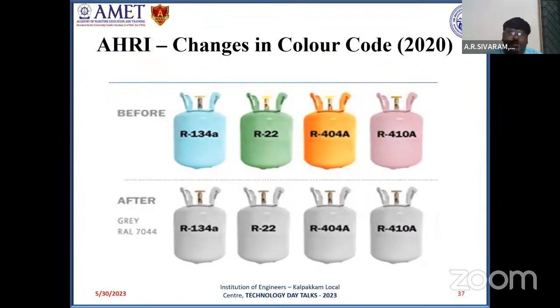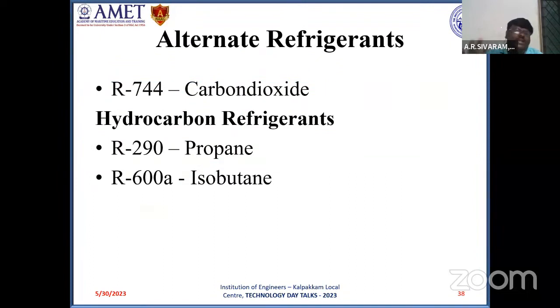Till the year 2020, the whole refrigerant cylinder was painted with the color of the refrigerant. In order to avoid painting complications and disposal of cylinders, AHRI made a change in the color code. The cylinders are now maintained uniformly in gray color. This change came into effect in the year 2020, and it was decided in the year 2017. Alternate refrigerants. So carbon dioxide. Carbon dioxide is a very good alternative to R134A and other HFCs, that is, the hydrofluorocarbon family of refrigerants.